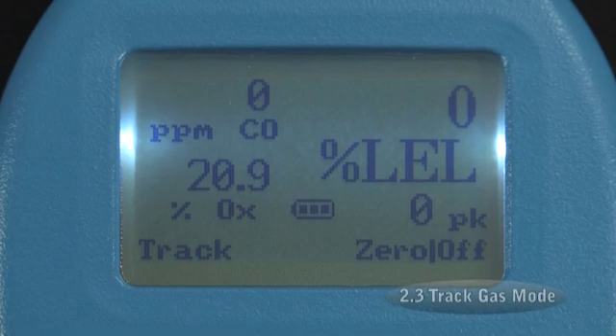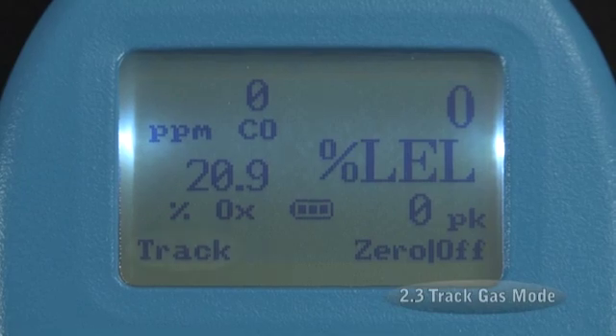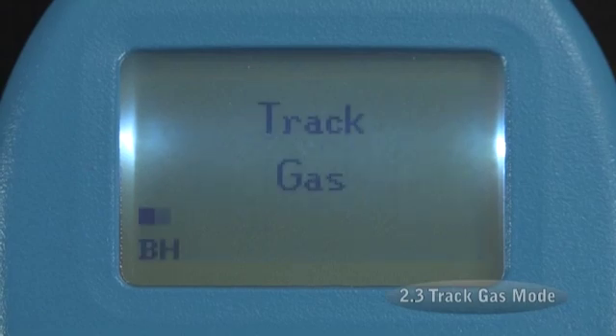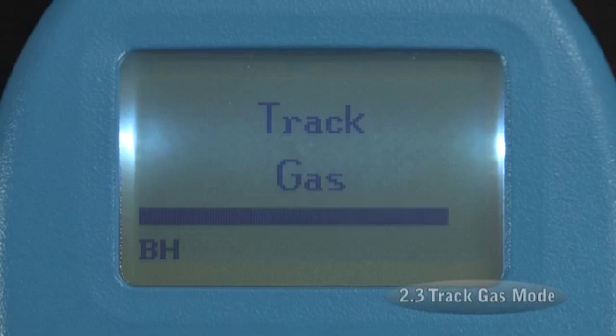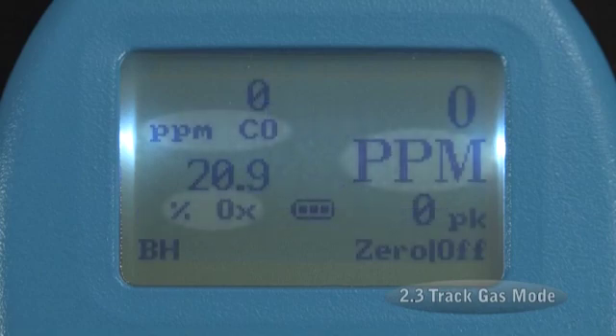From the monitor mode, press the left button marked Track to enter the track gas mode. You will see the words Track Gas on the screen and a scroll bar to indicate the machine is switching modes. As in the monitor mode, the track gas mode shows you all your sensor readings, but measures and displays gas in ppm instead of percent LEL or percent gas.